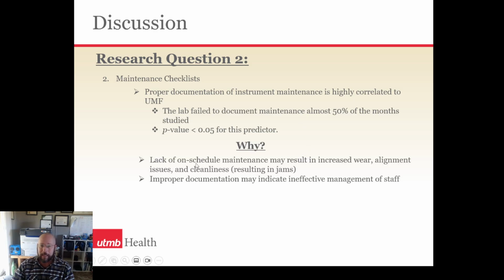Why is that? Primarily, it's this lack of on-schedule maintenance. There was an awful lot of on-schedule maintenance that either wasn't performed or wasn't documented. This is going to result in increased wear, alignment issues. There's cleanliness, resulting in a lot of the jams that you see in the cuvette system. And nobody could possibly make this idea, this correlation, that if we don't write our signature down on a log sheet, that's going to lead to mechanical failure.